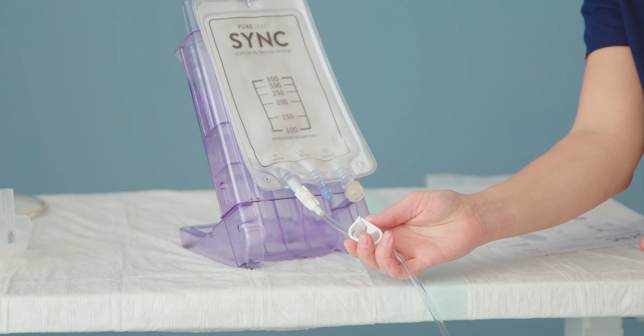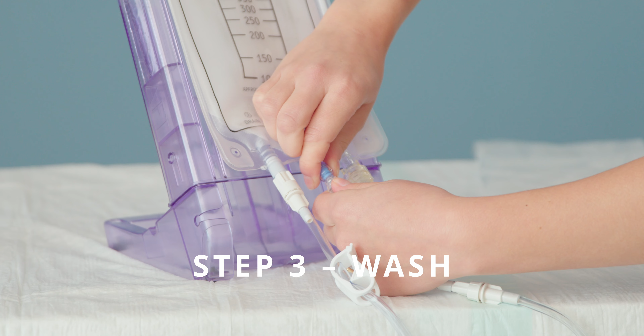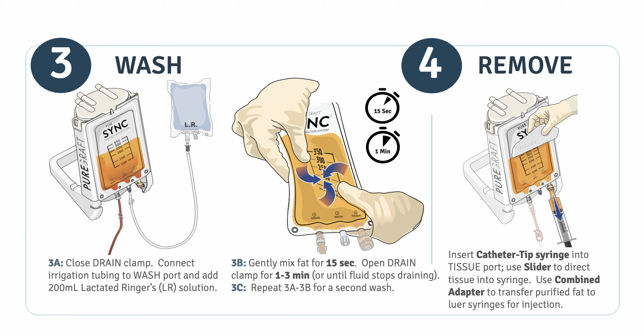While you are draining, you can get your wash fluid ready. After 1 to 3 minutes, close the drain clamp. Connect your irrigation tubing to the lactated ringer solution and to the wash port on the Puregraft filtration bag. Add 200 milliliters of lactated ringer solution to the Puregraft bag. Note that if you do not wish to use irrigation tubing, you can add wash fluid using Luer syringes through the wash port or using catheter tip syringes through the tissue port. After you have added your wash fluid, gently mix the fat for about 15 seconds. Then, open the drain clamp and allow fluid to drain for 1 to 3 minutes. At this point, your graft should be ready to use.